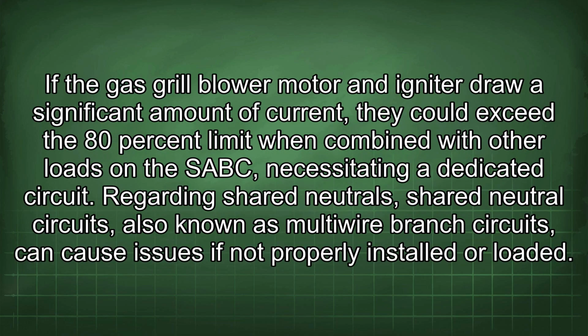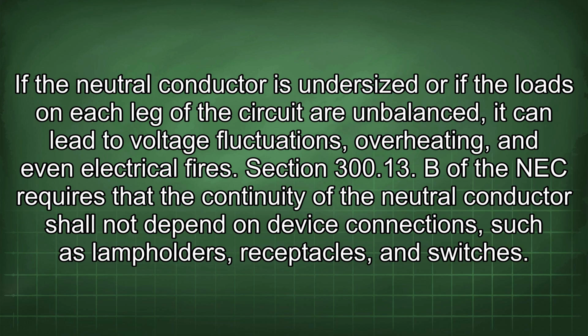If the gas grill blower motor and igniter draw a significant amount of current, they could exceed the 80% limit when combined with other loads on the SABC, necessitating a dedicated circuit. Regarding shared neutral circuits, also known as multi-wire branch circuits, they can cause issues if not properly installed or loaded. If the neutral conductor is undersized or if the loads on each leg of the circuit are unbalanced, it can lead to voltage fluctuations, overheating, and even electrical fires.